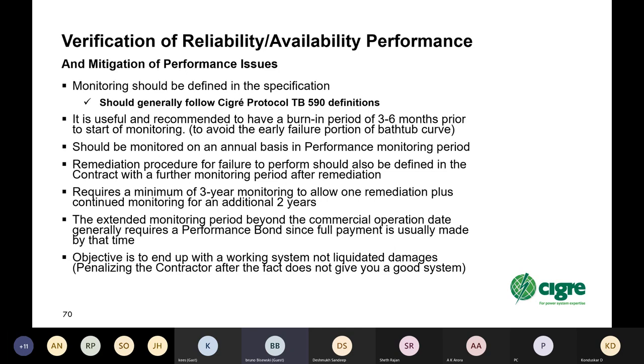And even afterwards, we encourage all users to monitor it on an annual basis and report to CIGRE so that the CIGRE reliability tracking can be updated, and new users, and even existing users, can benefit from reliability statistics on HVDC. Remediation procedure for failure to perform should also be defined in the contract, with a further monitoring period after remediation. That can require a minimum 3-year monitoring period to allow 1 year to monitor, some time to remediate, and then possibly two more years of monitoring to show that in fact you've got a reliable system in accordance with what you had intended to buy.